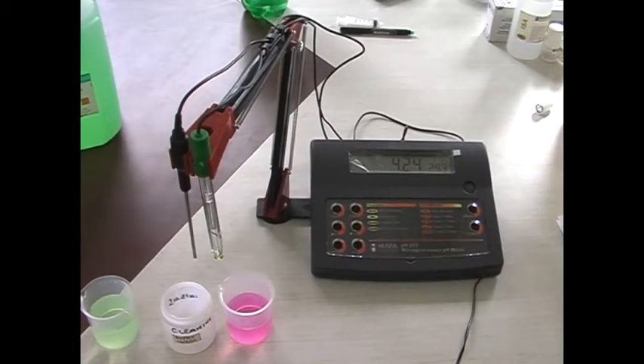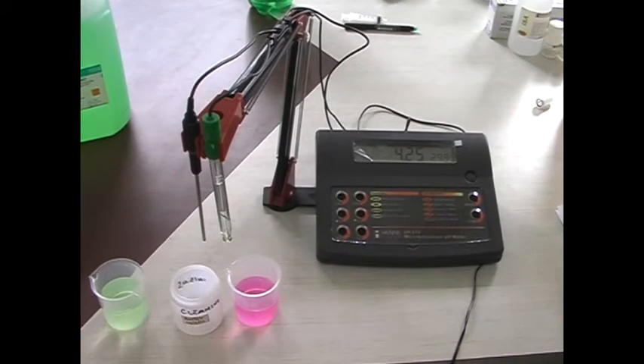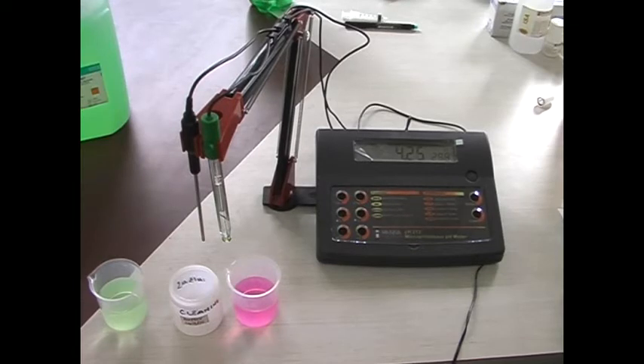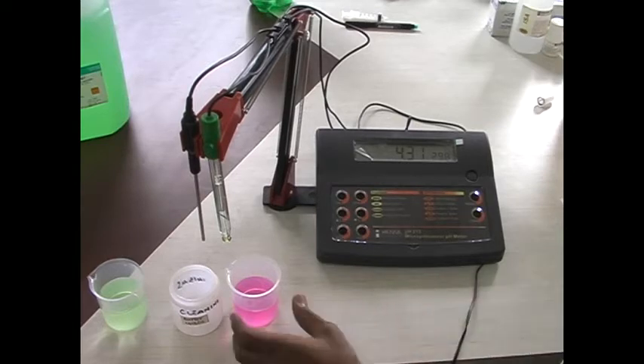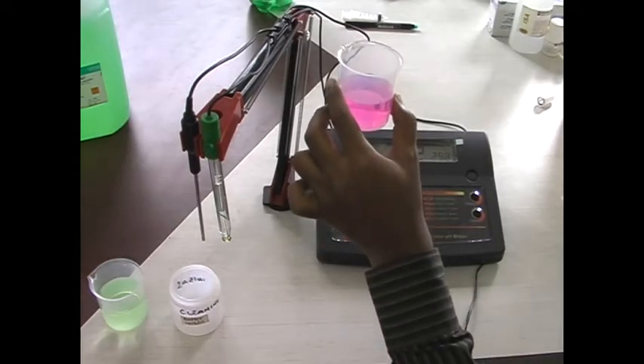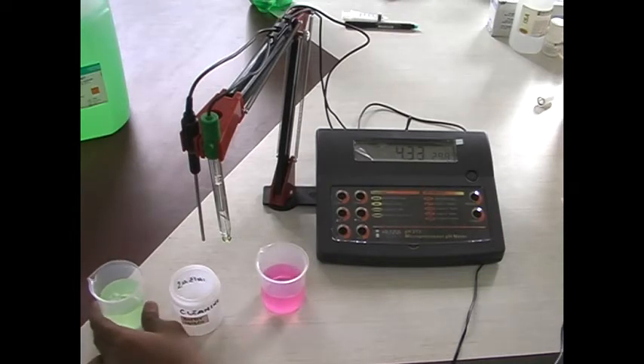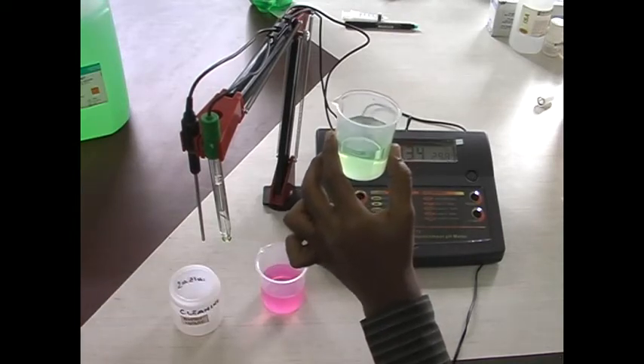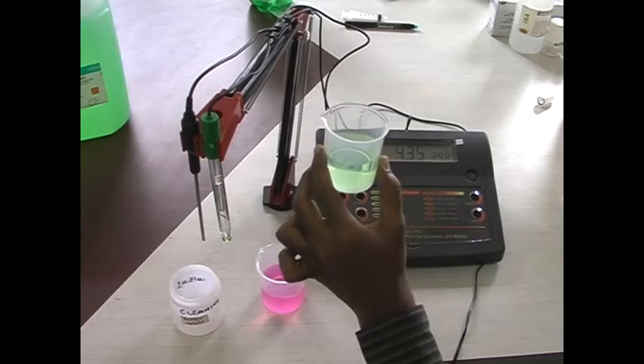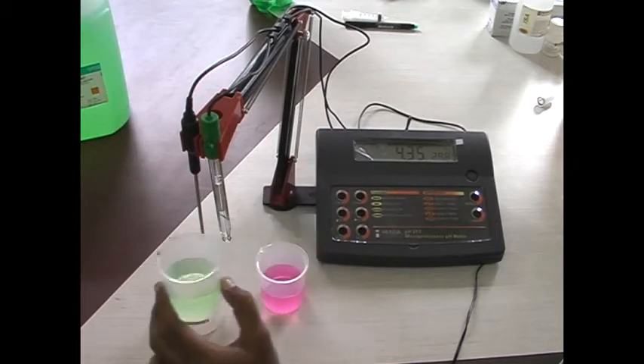Now we will learn how to calibrate this PH213. For the calibration, we require two solutions. Basically, the PH213 is a 2-point calibration. You can calibrate for 5 memorized buffers like 4.01, 6.86, 7.01, 9.18 or 10.01. Now we have this 4.01 buffer solution, and the 7.01 buffer solution. So today we are calibrating this instrument for 4 and 7. It is a 2-point calibration.